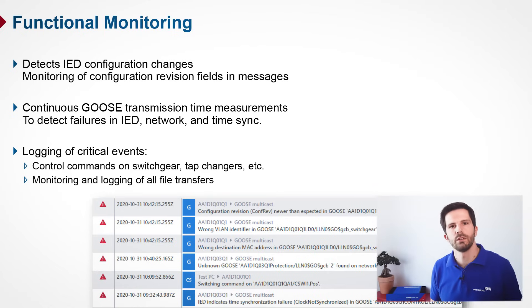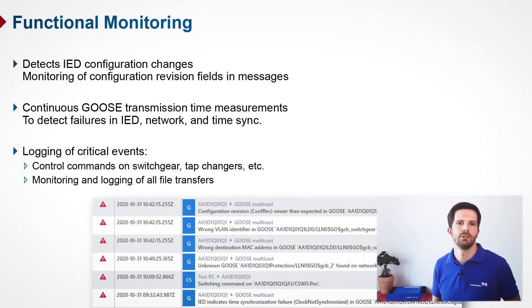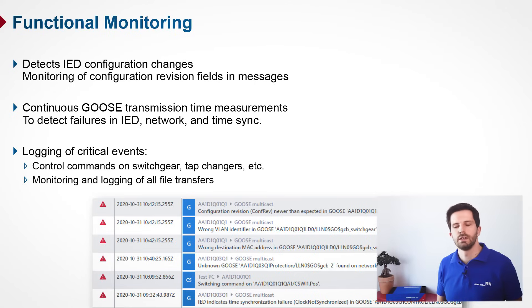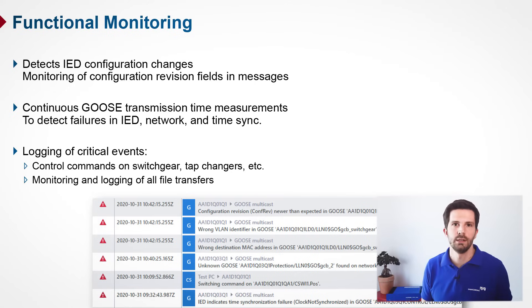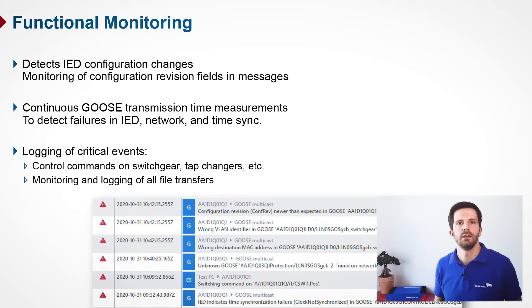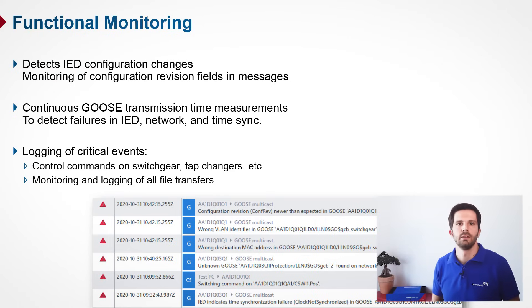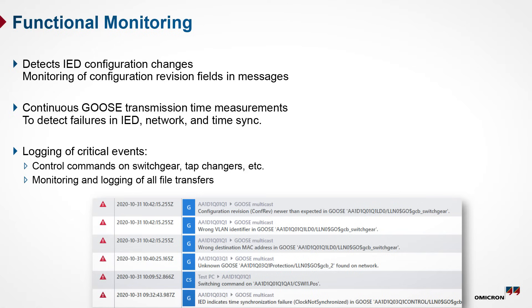Station Guard also continuously monitors communication and compares it with timestamps in messages to detect excessive transmission delays. This allows detection of denial-of-service situations in IEDs, network failures and delays, and most frequently, time synchronization errors in the substation. Station Guard can also log critical events such as switching operations, control commands, and file transfers including file names.